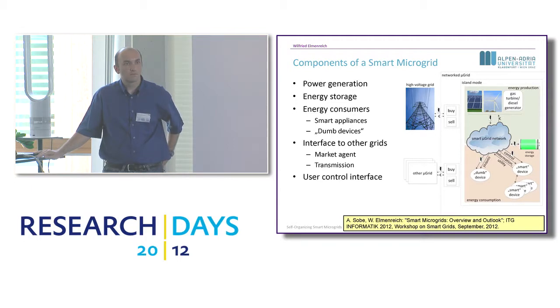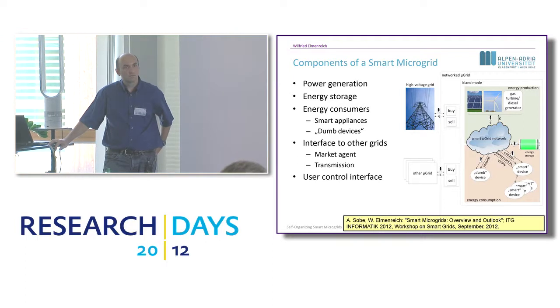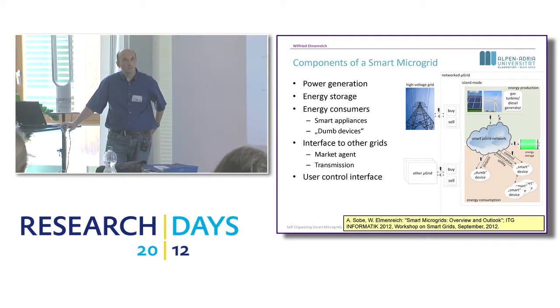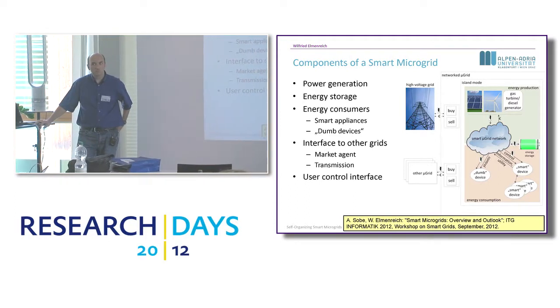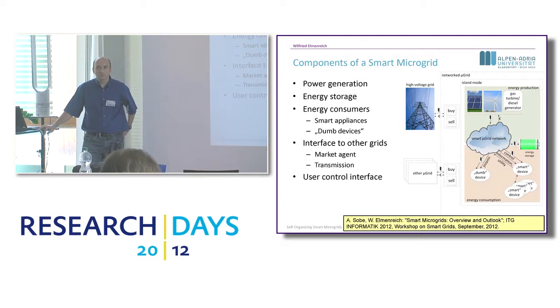But there could be an overlap, because if supply and demand is not matched, then you might get instability. Yes, of course. And supply demand matching comes close to the second part as soon as you go down in the time area. Then obviously the system cuts off and puts you in island mode, because you tend to stabilize the distribution network or wider area, and you go in island mode, and then you do your own balance in the microgrid, and then load shedding, no other way. You switch off unnecessary users if you happen to have a hospital, and it might be critical.